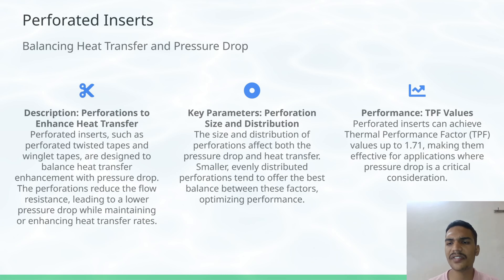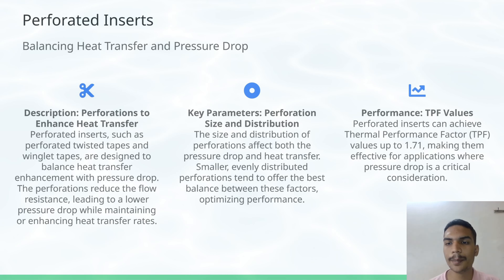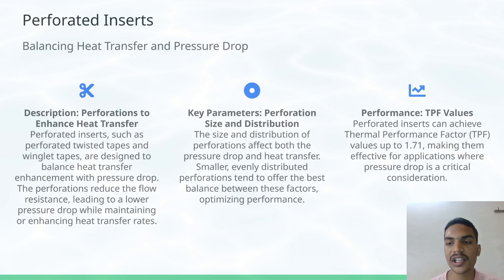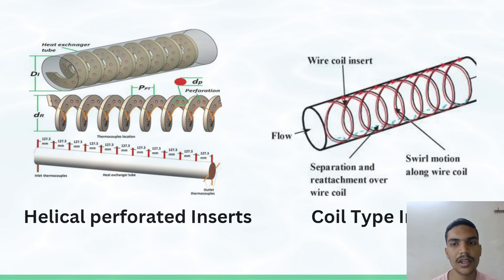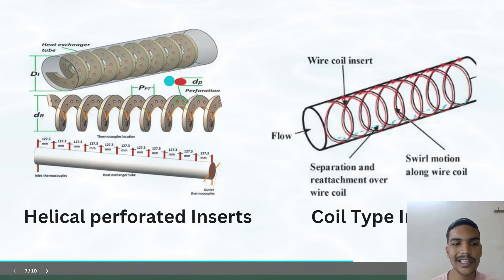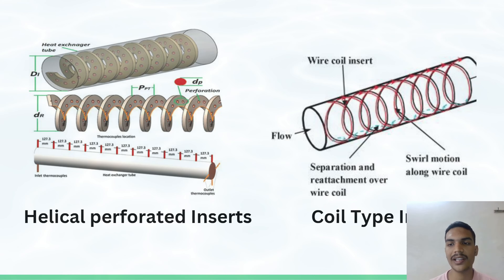Smaller but evenly distributed perforations tend to offer the best balance between these factors, optimizing performance. The TPF is generally up to 1.71, making them effective for applications where pressure drop is a critical consideration. You can see that a helical coil combined with perforations forms the coil-type insert discussed earlier.